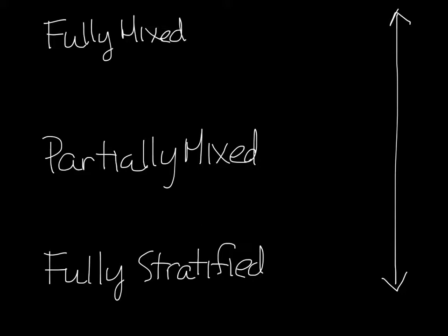In a mixed system, the supply air is mixed throughout the space. In a stratified system, the air movement is only driven by the buoyancy in the space. The classifications describe room temperature as elevation increases from floor to ceiling.